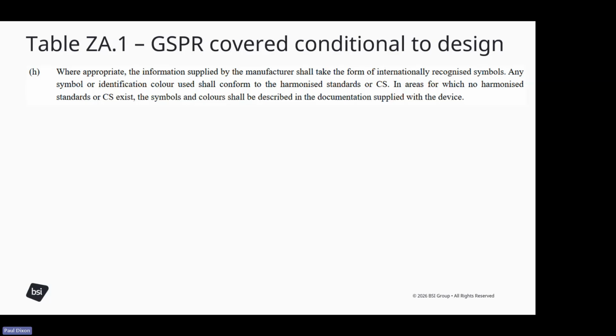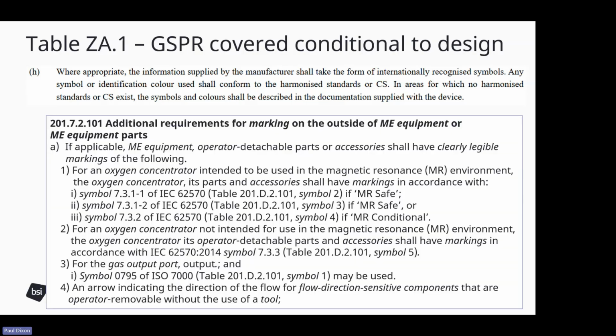Another example where a GSPR might be covered but conditional to design. This is actually 23.4H. Sorry, it's not very easy to tell that, but where appropriate information should take the form of internationally recognized symbols, and symbols and colors should conform to harmonized standards or common specifications. This is a clause from the oxygen concentrator standard that I've been using as an example, and you can see here that it's got references to symbols, symbol 7.3.1-1 and so on of an IEC 62570, which is the standard for marking for MR safety. There's also a reference to a symbol in ISO 7000.